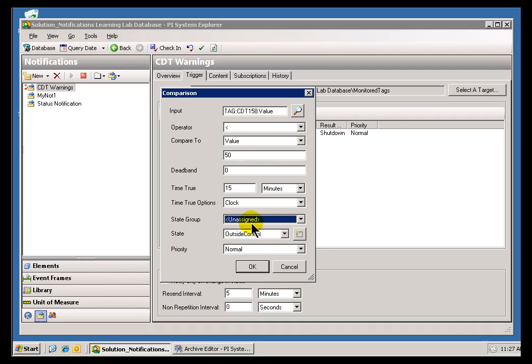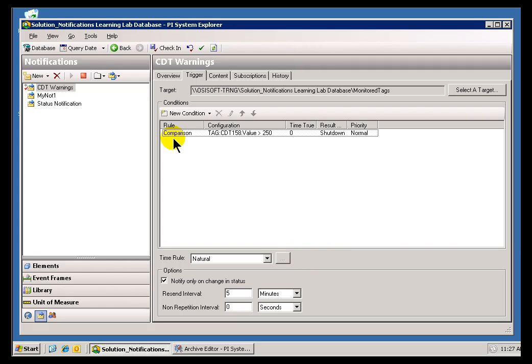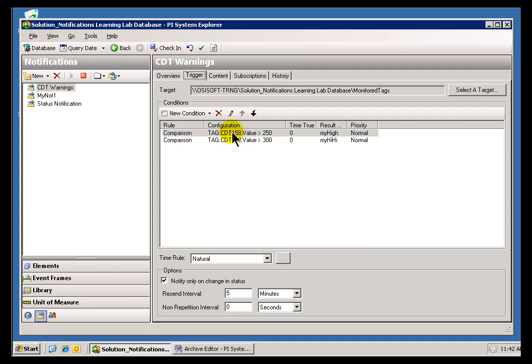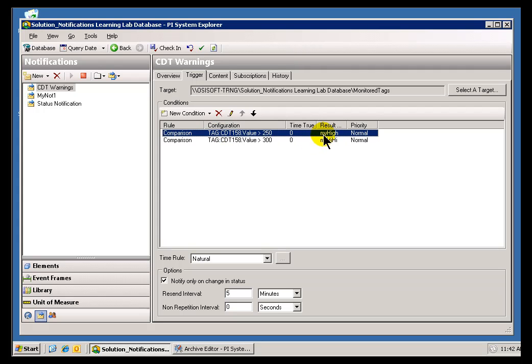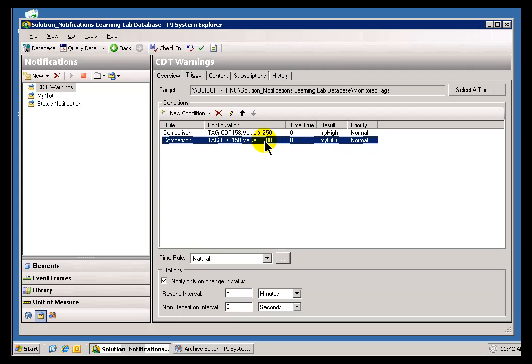Now, to really explain and demonstrate these State Groups and the States, what we need to do is go back and add another comparison to demonstrate what we mean by the different States, which is very useful when you've got multiple comparisons. Here's an example of a Notification that has two conditions resulting in two different Statuses or States — one called High and the other called High High. We're using High to indicate if it's over 250, and High High for greater than 300. This brings up a natural question: where did we get these results and where do they show up?